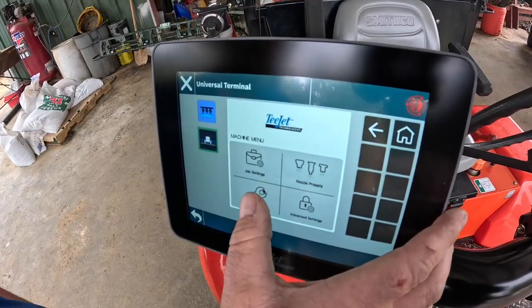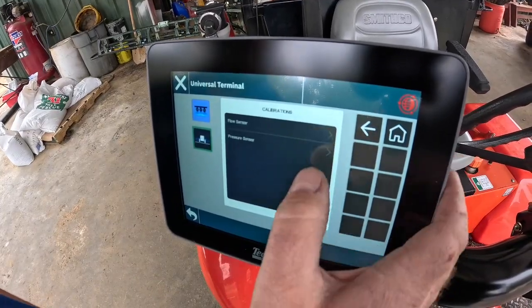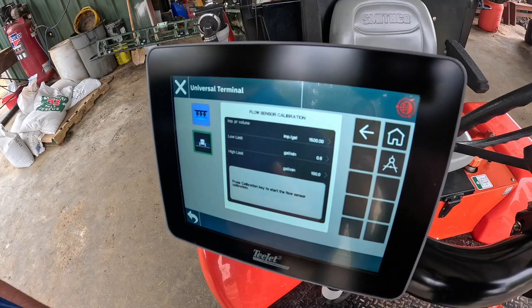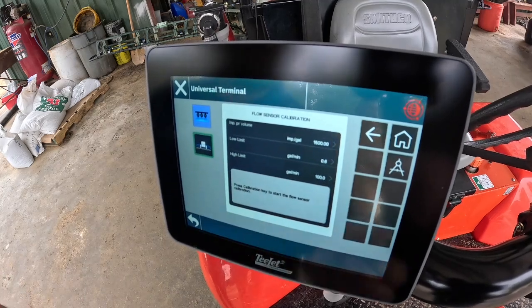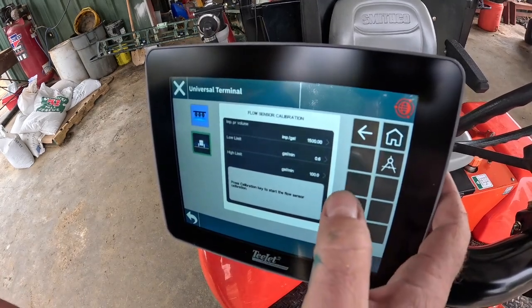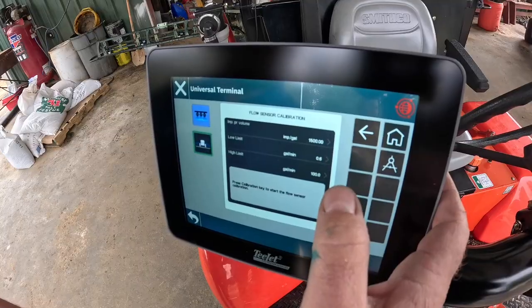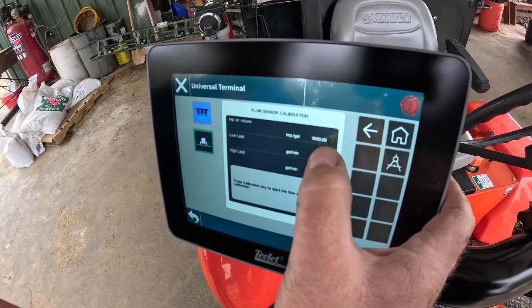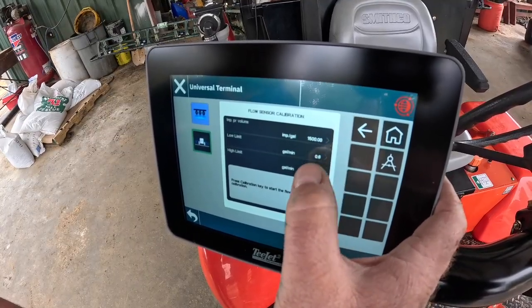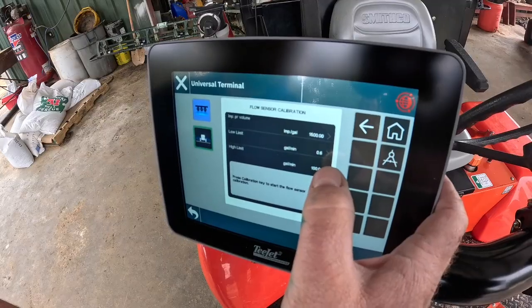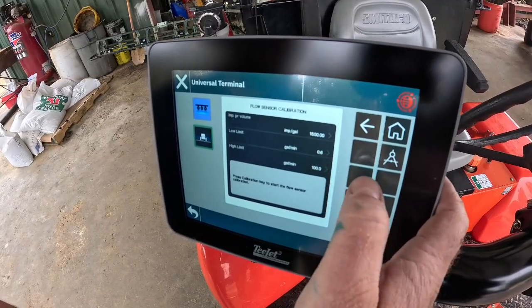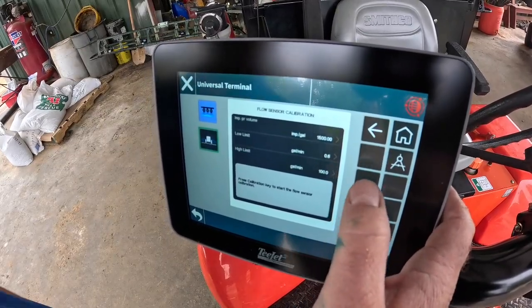Also here we have our calibrations. So your flow sensor, in this scenario, we have the TeeJet FM 9380, which is an electromagnetic flow meter, and it's 1500 pulses per gallon. It's on the tag on the flow meter. The low limit is 0.6 gallons per minute, and the high limit is 100, and both of those are also on the flow meter tag.